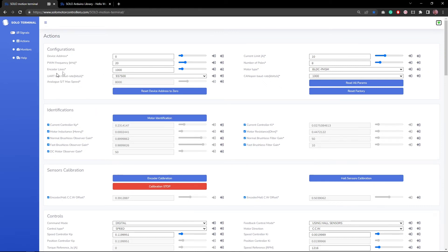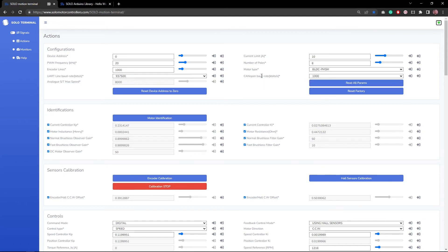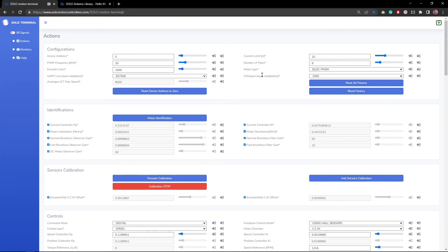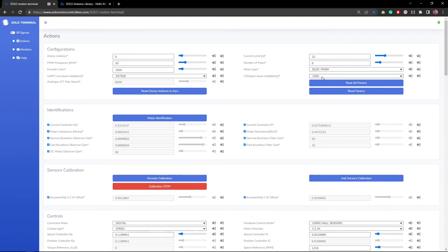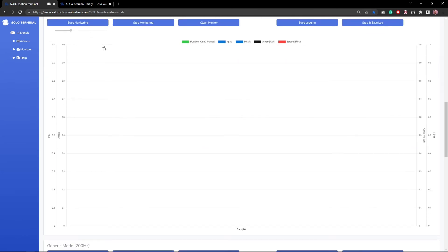You can set all the parameters that you already set in the code also in motion terminal. Most of the parameters like the motor type, the switching frequency or any other parameter that you saw there you can also set them here but this is not what I'm gonna do. I'm just gonna tell you that the CANOPEN baud rate actually can be set through motion terminal through this parameter that you can see here. Right now we are operating at one megabit per second but you can change it.